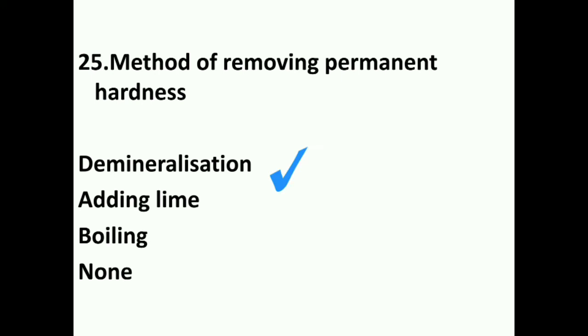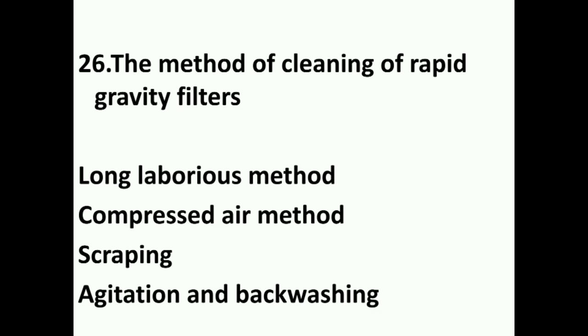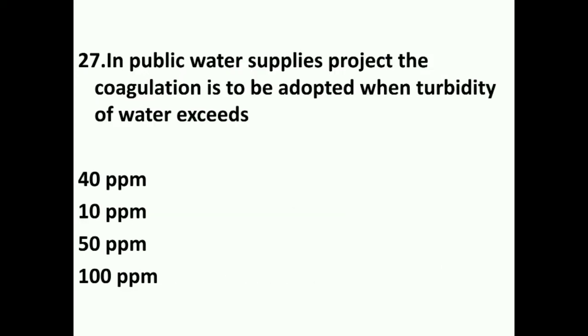Method of removing permanent hardness: the demineralization process. Lime addition and boiling are used for temporary hardness removal. Method for cleaning rapid sand filters: the cleaning method is backwashing — specifically agitation and backwashing. Scraping is used in slow sand filters. In public water supplies, coagulation is adopted when the turbidity of water exceeds 40 ppm.